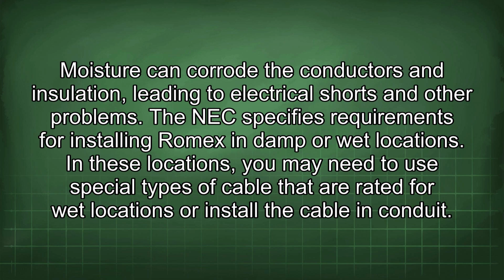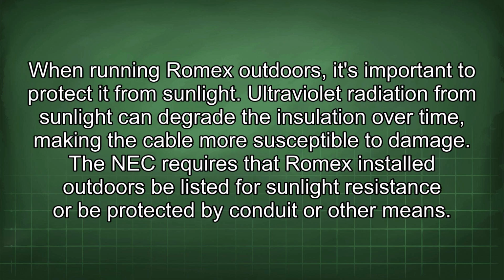the cable in conduit. When running Romex outdoors, it's important to protect it from sunlight. Ultraviolet radiation from sunlight can degrade the insulation over time, making the cable more susceptible to damage. The NEC requires that Romex installed outdoors be listed for sunlight resistance or be protected by conduit or other means.